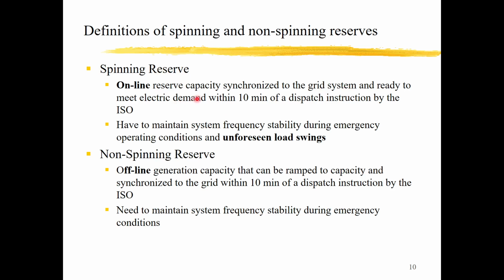The power can be supplied to the grid within 10 minutes from the dispatch instruction by the ISO. ISO means independent systems operator. They will give the command to the reserve system, and it will respond in 10 minutes for the spinning reserve. For the non-spinning reserve, it is basically offline and not synchronized, but after receiving the dispatch instruction, it also has to respond and synchronize to the grid within 10 minutes. Okay, the same. The difference is that one is already online and the other is not. And they have to maintain system frequency stability during emergency conditions or unforeseen load swings.